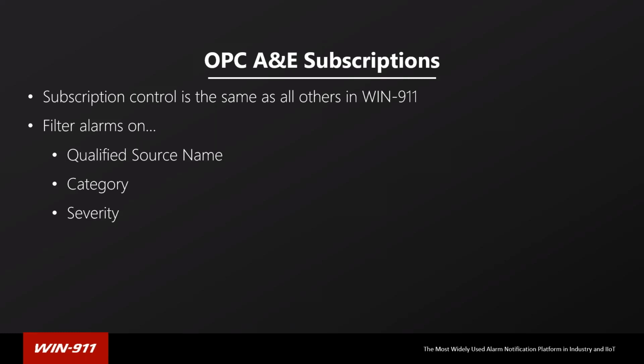Category and severity. Category is, I thought I had a thing in here to describe category, but I don't think I do. It's a way that the tags themselves are sorted within an A&E server, so each A&E server can have a different categorization for those alarms. So, for example, one categorization could be level alarms, and so if you subscribe to that category, you're going to get all level alarms, and one may be Boolean alarms, and if you subscribe to that, you're going to get all Boolean alarms. And then severity is the last one.